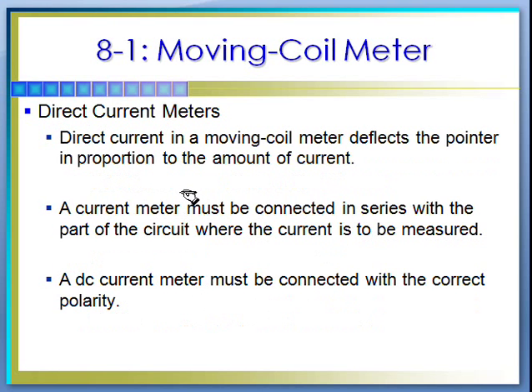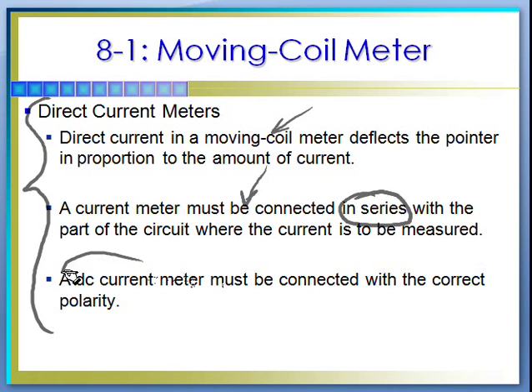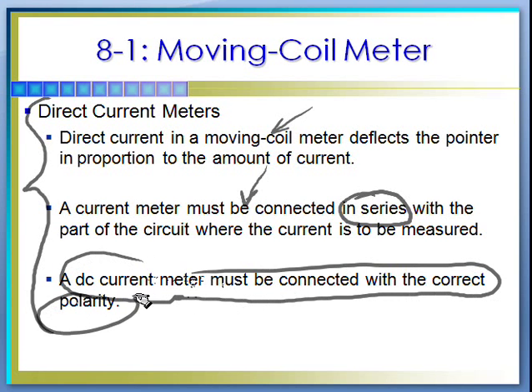When we are using the current meter function — in this case a DC direct current meter — the direct current in a moving coil meter deflects the pointer in proportion to the amount of current you're putting through it. The current meter must be connected in series with the part of the circuit you're measuring, whether it's analog or digital. To get the right reading, you have to be connected with the correct polarity — your negative side goes to your lowest potential, your positive side to your higher potential.